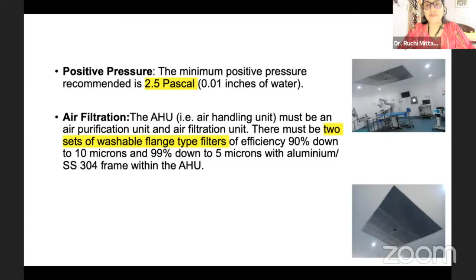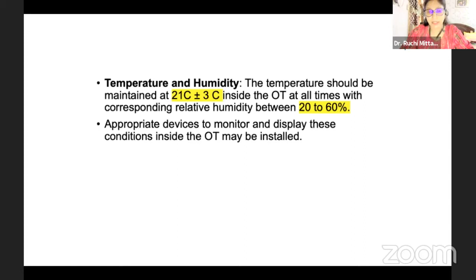Now, temperature and humidity again are very important. The temperature should be maintained at 21 plus or minus 3 degrees Celsius inside the OT at all times, and relative humidity between 20 to 60%. And remember, we should have appropriate devices to monitor and display these conditions inside the OT. There is no size restriction of the OR in case of remodeling, but there should be sufficient space for the movement of the staff.